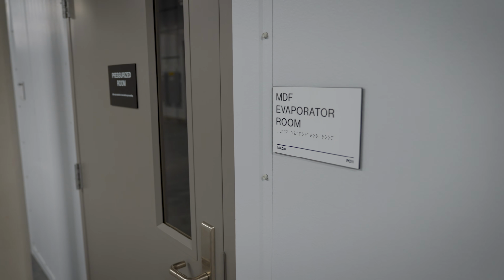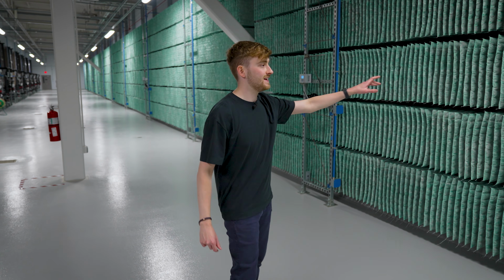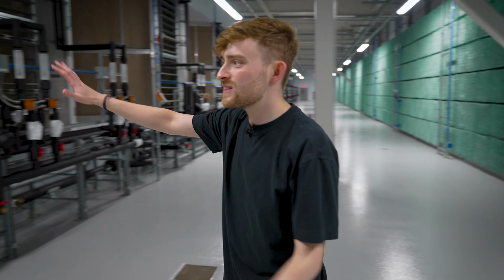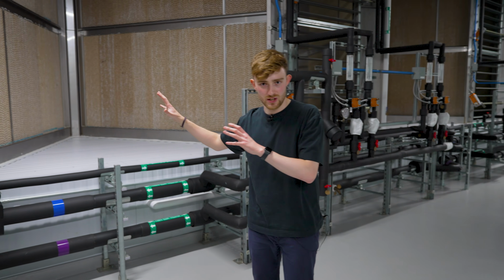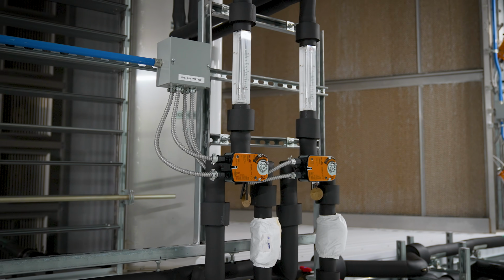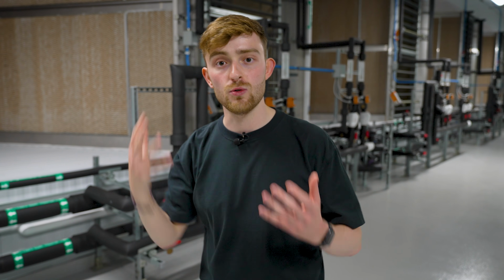Step 3 begins exactly where we left off, which is the clean air coming through these filters and then being passed into what looks kind of like a honeycomb structure. This honeycomb structure isn't really in use at the moment because, like I said, water isn't being used throughout these certain months within the year. But when it is, water is being pumped into this honeycomb structure to allow the air to pass through it and cool the air down.